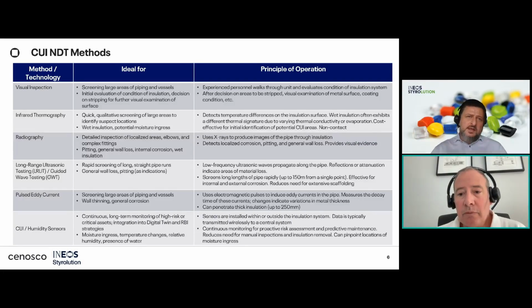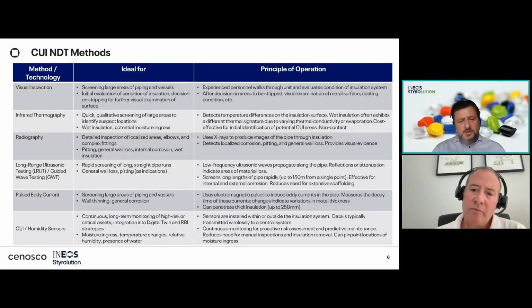I even have an example where we had similar equipment in different locations of the world. One was in Texas, where it's warmer than in Central North Europe. And there we removed the insulation, or my colleagues removed the insulation and applied a thermal insulation coating. I think it was from Mascoat, the company. It's a few millimeters thick, doing both the work of the coating and the insulation, so you don't need a cladding, and you can see it if it gets damaged.